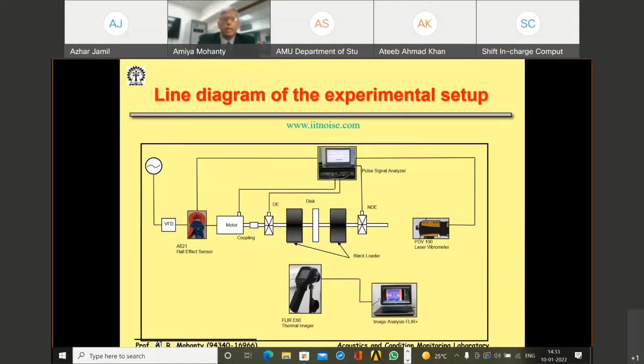So what we did, this is a setup which we have in the laboratory. We have a motor coupling driving a shaft supported on bearings. We measured the current, we measured the thermal imaging with a FLIR E60 camera. We looked at the analysis, we measured the vibration. This is the setup: a thermal imaging camera put on a tripod, this is the rotor, these are all lasers, and this is the thermal imaging camera.